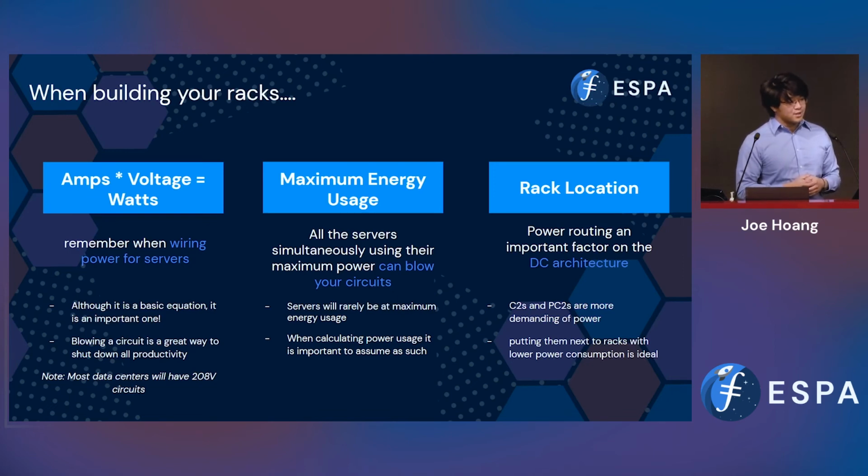As an example, let's say you have a 20 amp circuit, and then most data centers will provide you with a roughly 208 volt circuit as well, giving you about 4,160 watts of power. But another thing I want to mention on top of that is that places will often have a fire marshal standard, typically I think set around 80%. So instead you'll have 3,300 something watts of power for usage rather than the maximum amount. However, going over that and you're almost quite literally playing with fire.